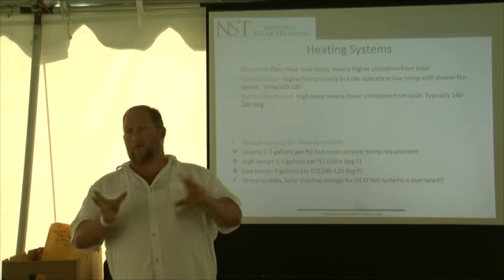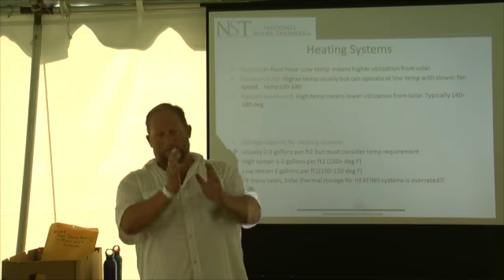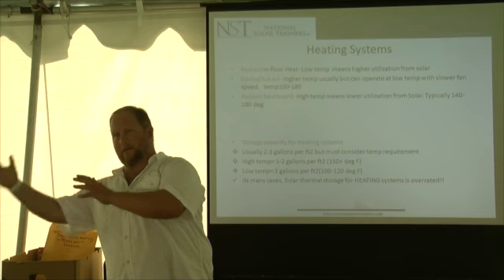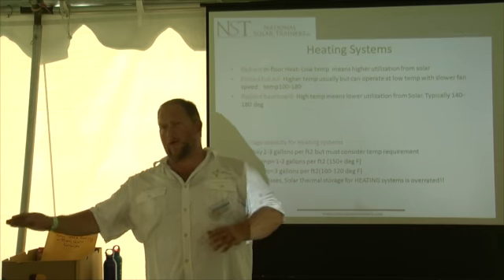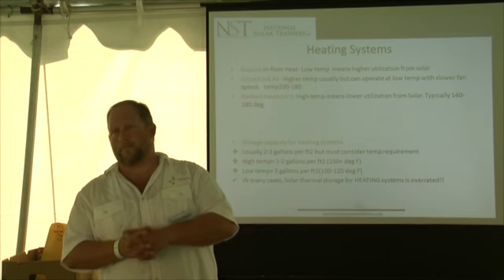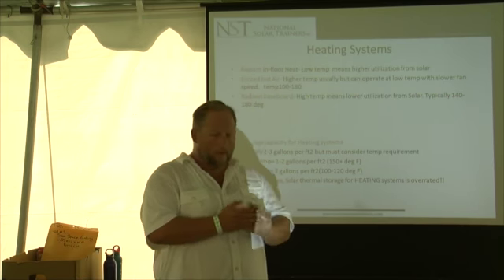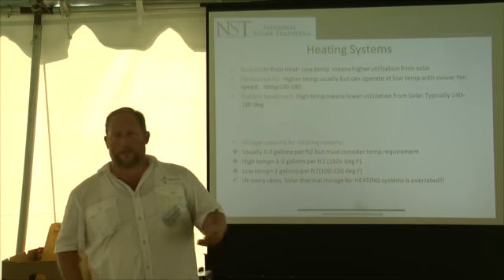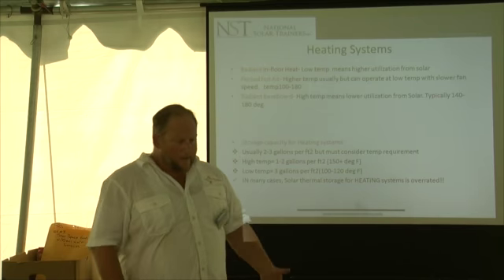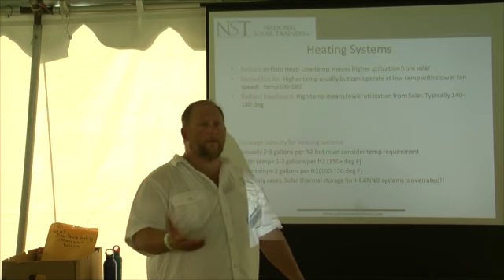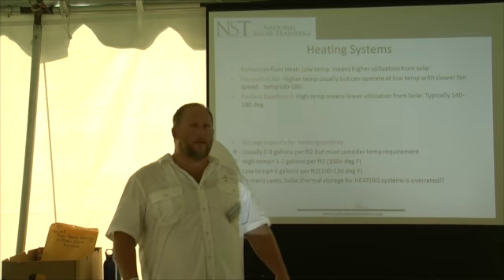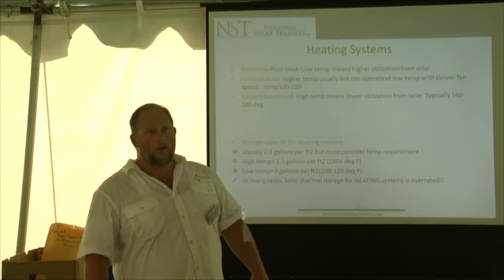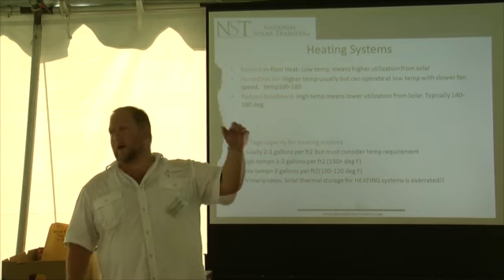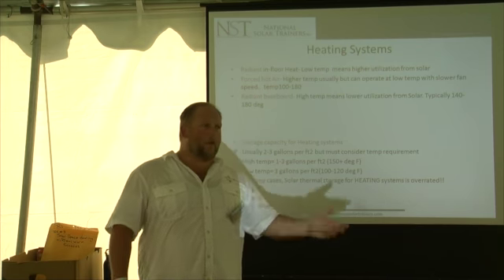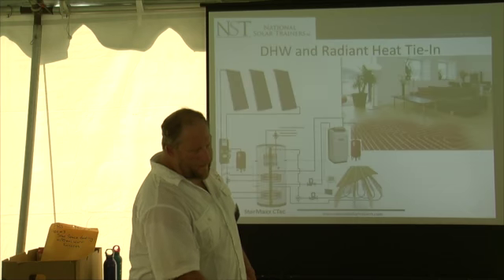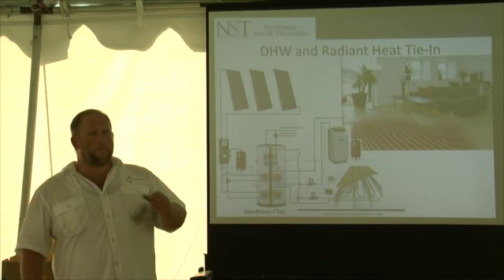It's different than going from the collectors through a heat exchanger, from the heat exchanger to the tank, from the tank to the radiant baseboard. You're going direct. So you're already benefiting. Okay, and the collectors are a heat exchanger in themselves. Okay, so radiant baseboard, it's a very ineffective way to heat the home with solar. Why? Because the temperature set point is so high. The higher the set point, the lower the utilization of the collectors. Okay? Can you explain that again?